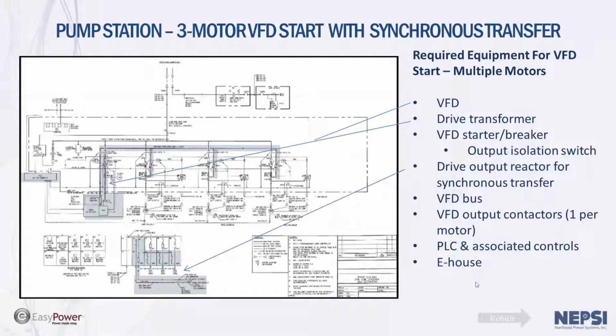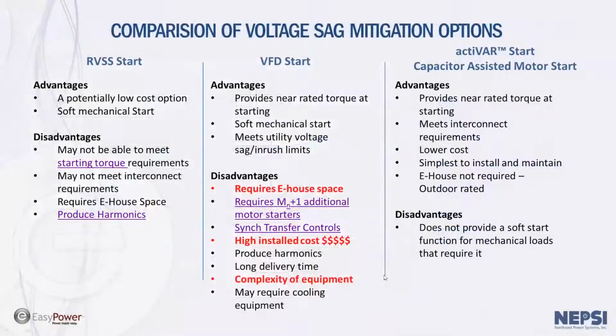This all has an associated cost with it. The sync transfers are typically custom controls and require custom programming of PLCs. The commissioning process can be quite complicated. So it is a more costly option and a much more complex option when compared to a reduced voltage soft start option. It does have the advantage that it will meet utility voltage sag limits and inrush limits. You get a soft start option, which is also nice because you can reduce the voltage and the frequency of the motor and basically start at full torque and meet the utility voltage sag limits.